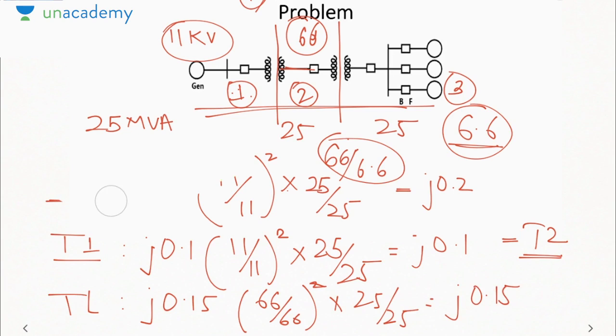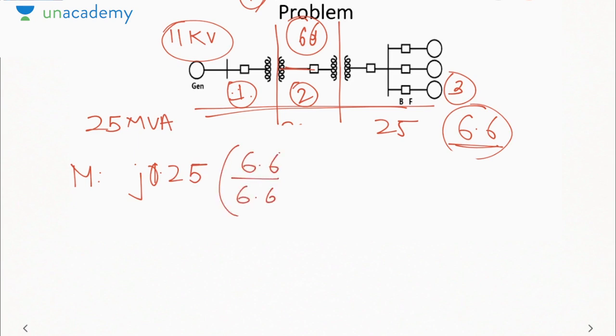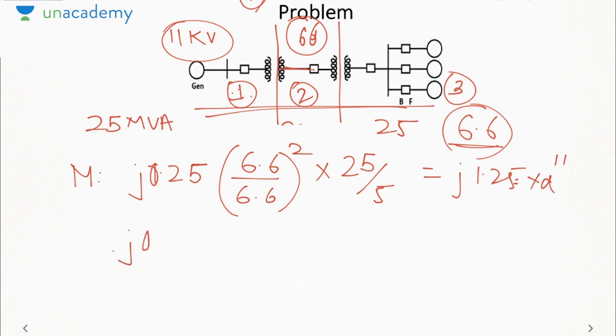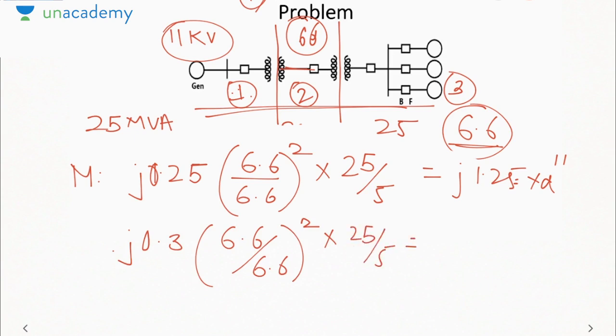Now for the case of the motor, the voltage that is given at the motor terminals is 6.6 kV and we have also assumed 6.6. So given is j0.25, 25%. The voltage that is given is 6.6, we have assumed 6.6. The base that we have assumed is 25, given is 5. So it will be j1.25, which is equal to X_d double dash. Similarly, the transient reactance will be j0.3. 6.6 is given, assumed is also 6.6. 25 is assumed, 5 is given. So it will be j1.5. That will be X_d dash.